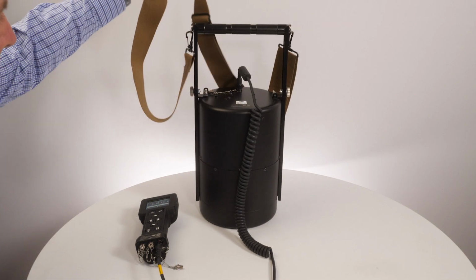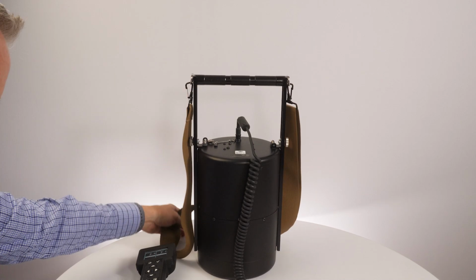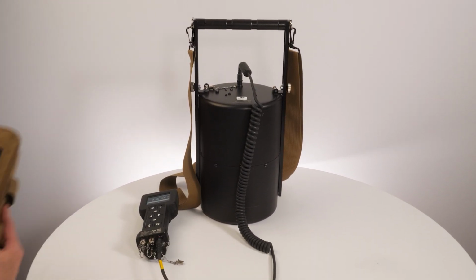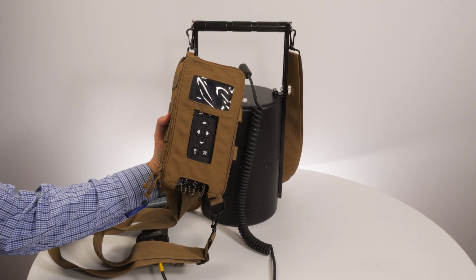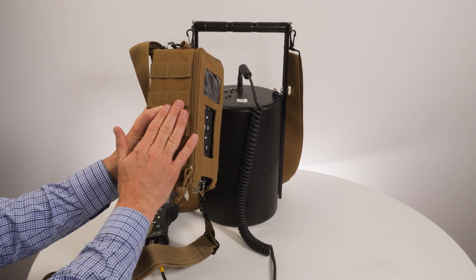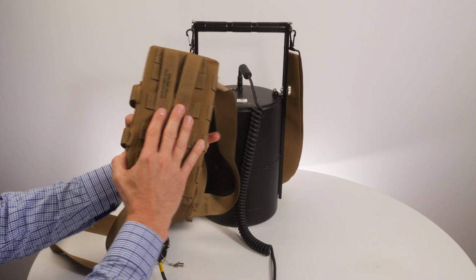There is a shoulder strap for the probe that is meant to help support the weight of the probe and keep it from being dropped. While conducting surveys with the FIDLER probe, use of the base unit carrying pouch is recommended, either worn with the shoulder strap across your body or attached using the MOLLE attachment methods to your belt or vest as desired.